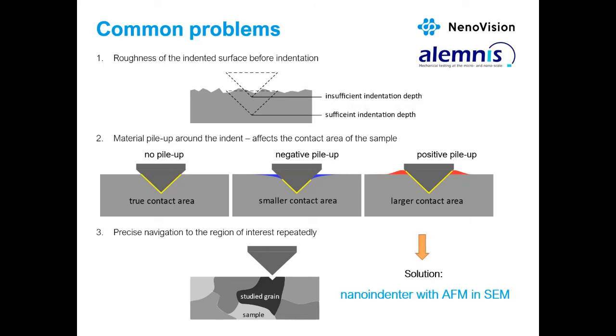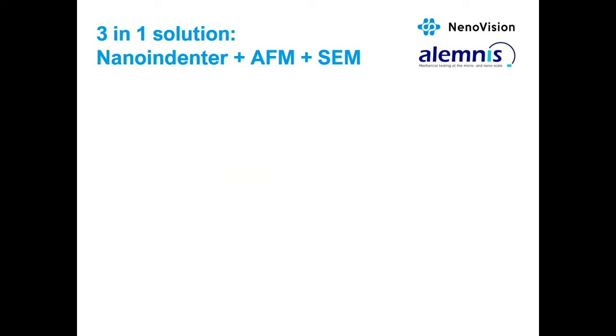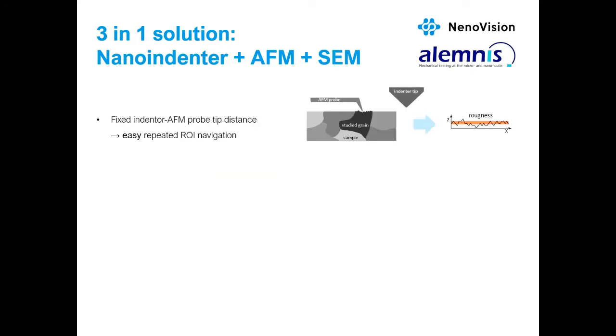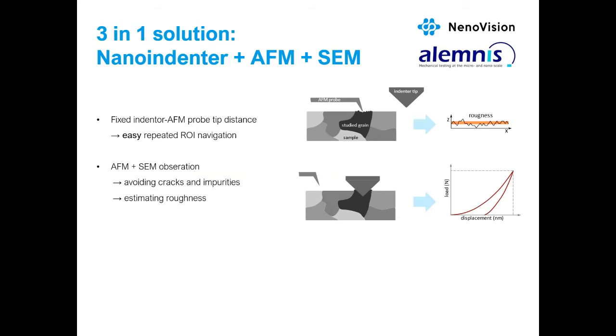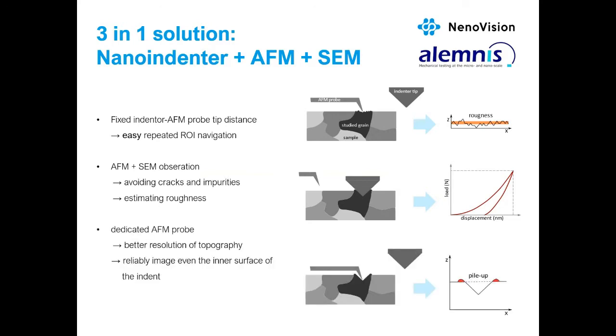The solution overcoming these problems is the 3-in-1 Nanoindenter with AFM in SEM. So the optimized procedure is to localize the area of interest, measure the roughness by AFM, avoiding any cracks or impurities using the SEM observation. Then we make the nanoindentation tests, and using high-resolution AFM, we measure the indents for the real depth and pile-up effects, etc.